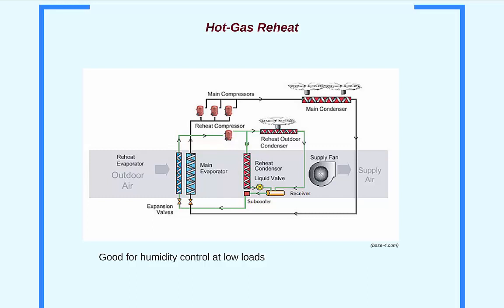As humid outdoor air passes over the main evaporator, moisture condenses out of the airstream and the temperature decreases. As the airstream passes over the reheat condenser, only the temperature is increased. Now the supply air distributed to the zones has significantly less humidity than the outdoor air, but the air temperature is only slightly lower.